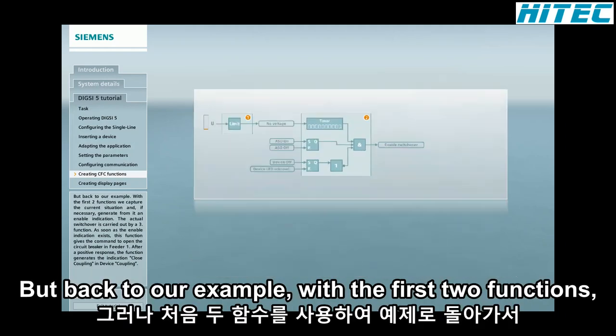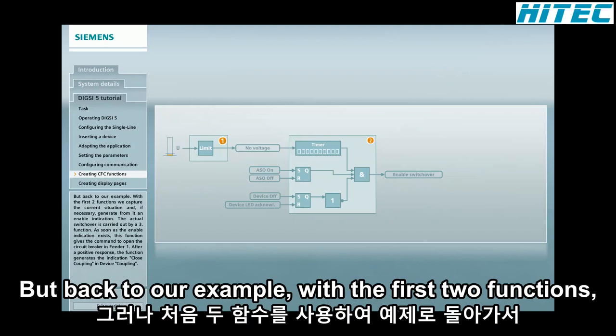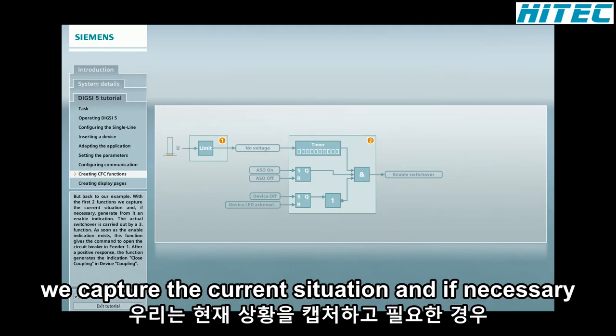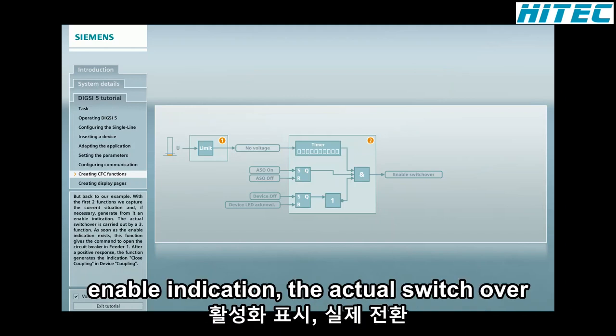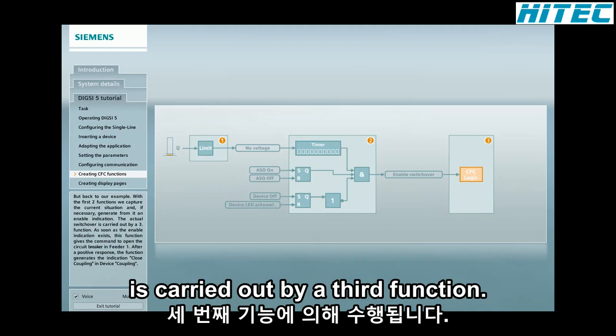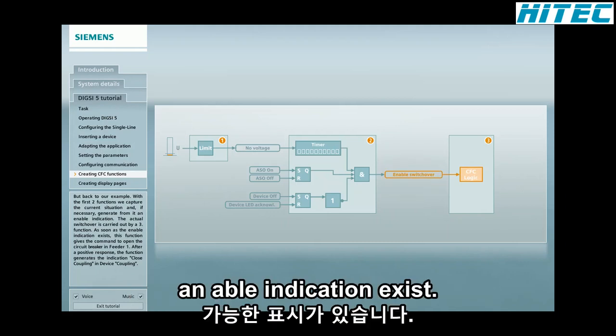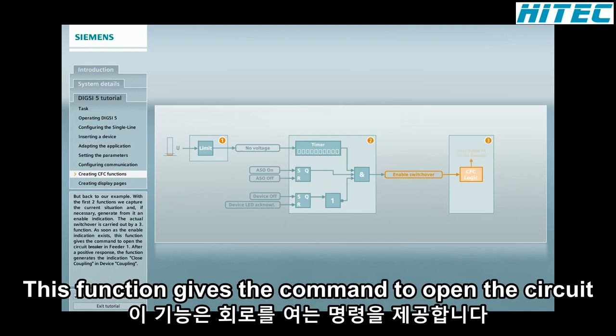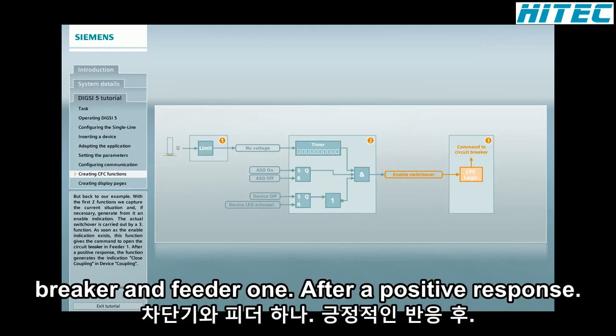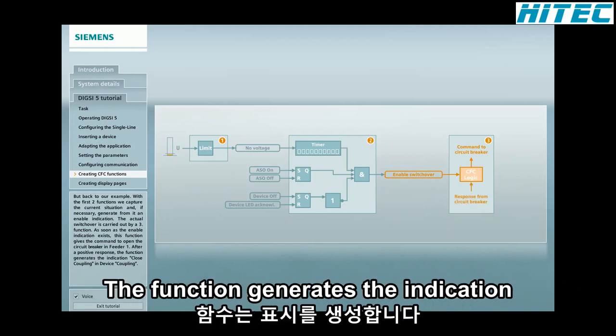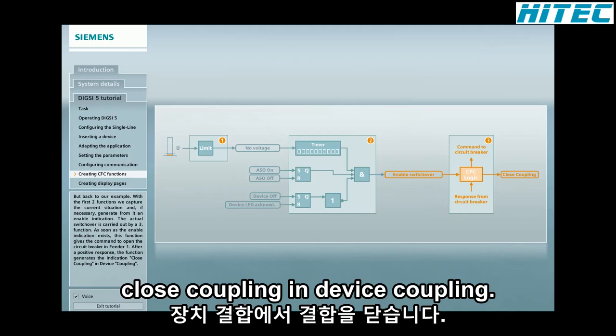But back to our example. With the first 2 functions, we capture the current situation and, if necessary, generate from it an enable indication. The actual switchover is carried out by a 3rd function. As soon as the enable indication exists, this function gives the command to open the circuit breaker in feeder 1. After a positive response, the function generates the indication close coupling in device coupling.